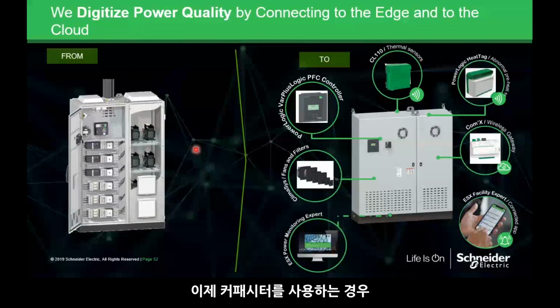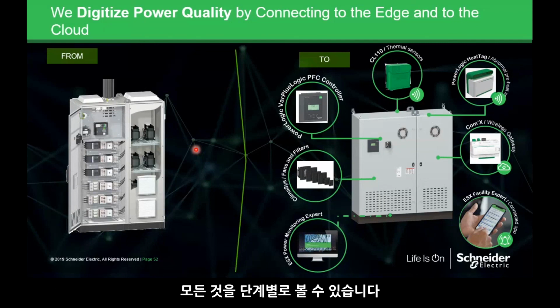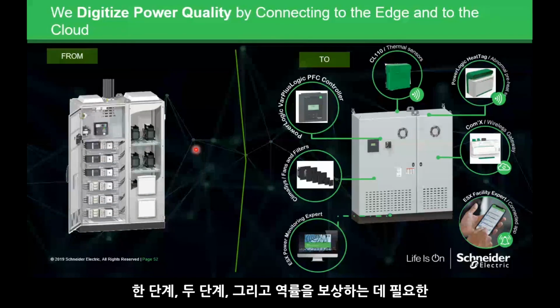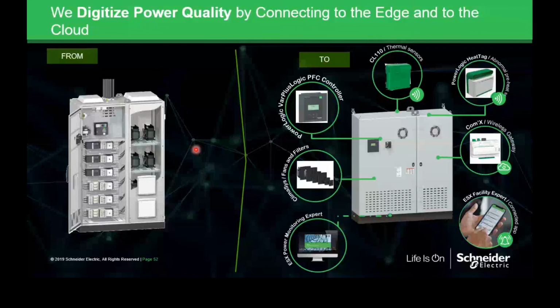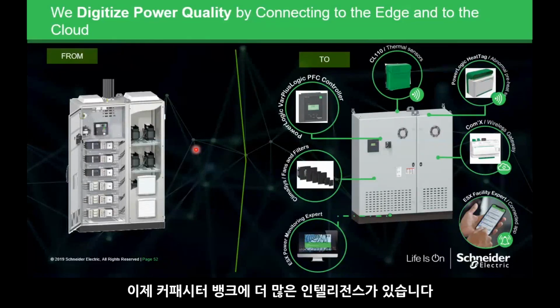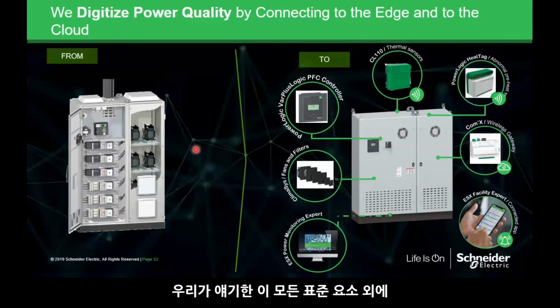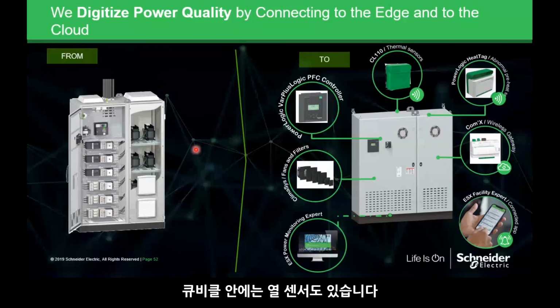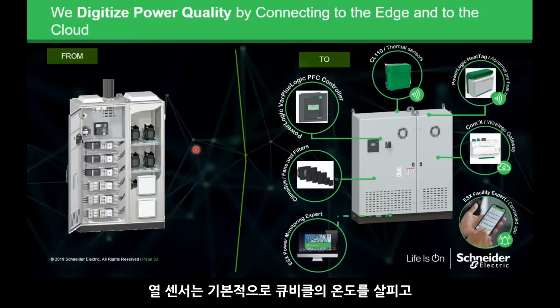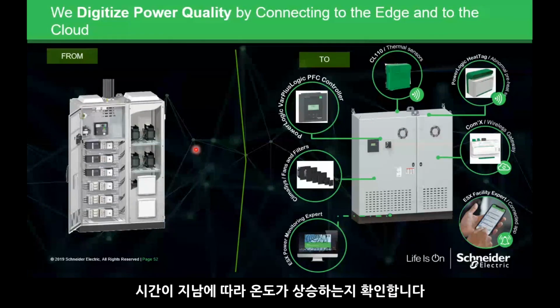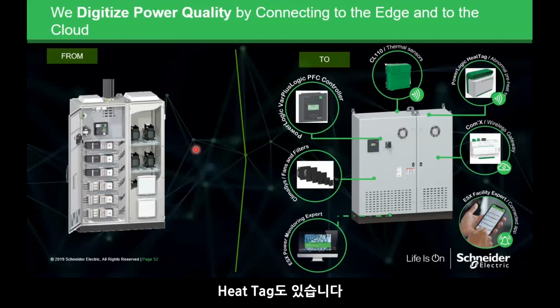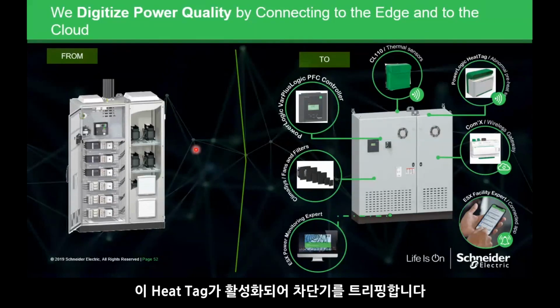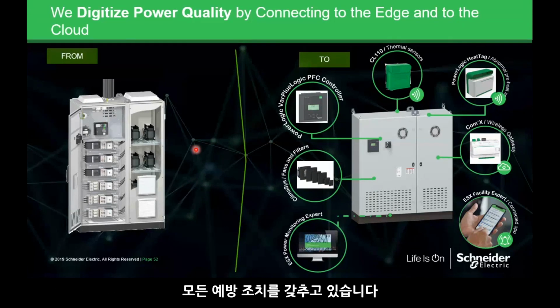Today the conventional capacitor bank basically has capacitor cans, controllers and reactors. Everything goes by steps: 1 step, 2 steps, and then you cut in however many kVAR are required to compensate the power factor. But moving forward, there is more intelligence in the capacitor bank. Besides the standard things I've talked about, we also have thermal sensors inside the cubicle, which look at the temperature of the cubicle and whether there is any rise of temperature over time. We also have a heat tag. When anything starts to burn and the temperature starts to rise, the heat tag is activated and trips the breaker.